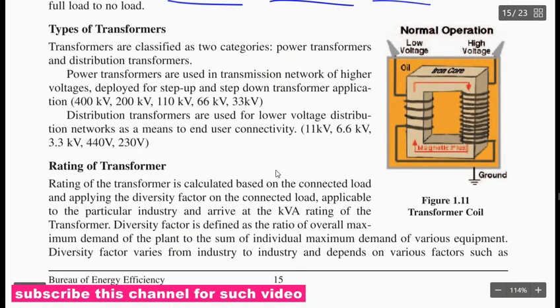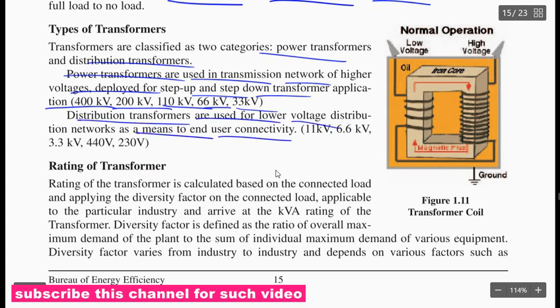Types of transformer. Transformers are classified into two categories: power transformer and distribution transformer. Power transformers are used in the transmission network of higher voltage, deployed for step up and step down transformer application: 400 kV, 220 kV, 110 kV, 66 kV, 33 kV. Distribution transformers are used to supply lower voltage systems as a means of reaching the end user: 11 kV, 6.6 kV, 3.3 kV, 400 and 230 volt. Rating of transformer.